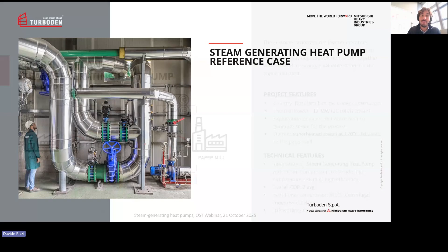We are in an industrial field, talking about a heat pump in a paper mill in North Europe. From this simplified scheme, the heat source is wastewater coming from the paper production, with an average temperature in the range of 17 degrees C, which is then cooled down to around 8 degrees C.